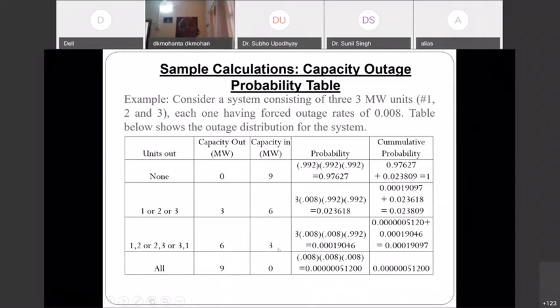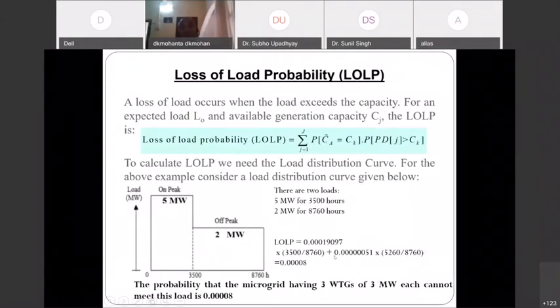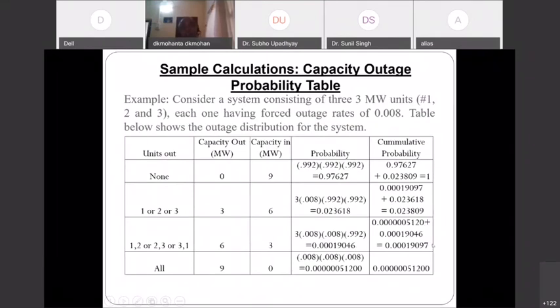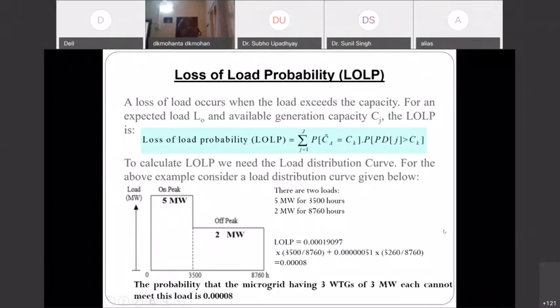And what is the cumulative probability for a 6 megawatt outage or more, or 3 megawatt capacity or less? It is 0.00019097. Now, what is the duration for which this probability exists? My total duration is 8760 hours, and out of that, the 5 megawatt load exists only for 3500 hours. So this is the ratio of 3500 to 8760, because this is the duration for which this load exists. This factor is basically the generation not meeting the load. If the capacity is 3 megawatt and my load demand is 5 megawatt, this is the probability that load will not be met by generation, and the probability of time is 3500 out of 8760.